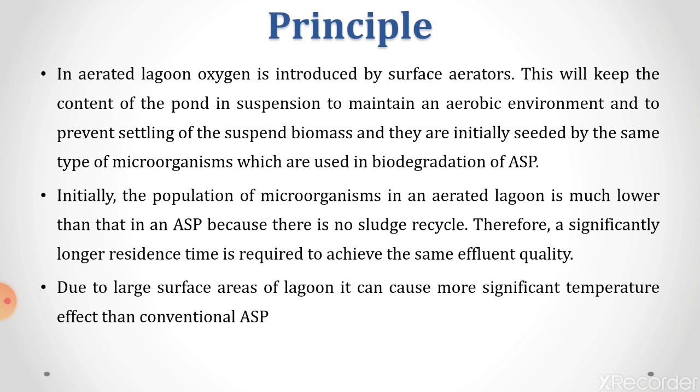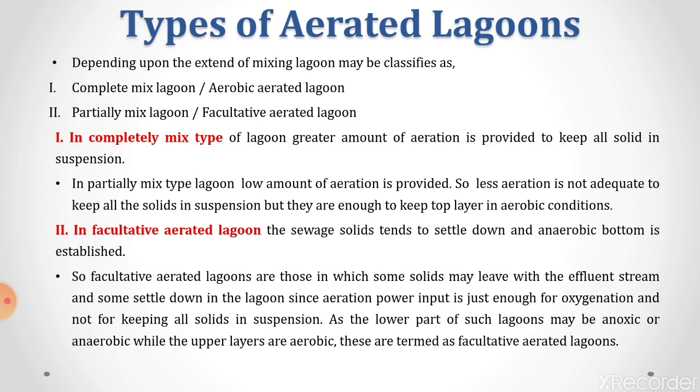Initially, the population of microorganism in an aerated lagoon is much lower than that in the ASP because there is no sludge recycle. Therefore, a significantly longer residence time is required to achieve the same effluent quality. Due to the large surface area of the lagoon, it can cause more significant temperature effect than the conventional ASP.